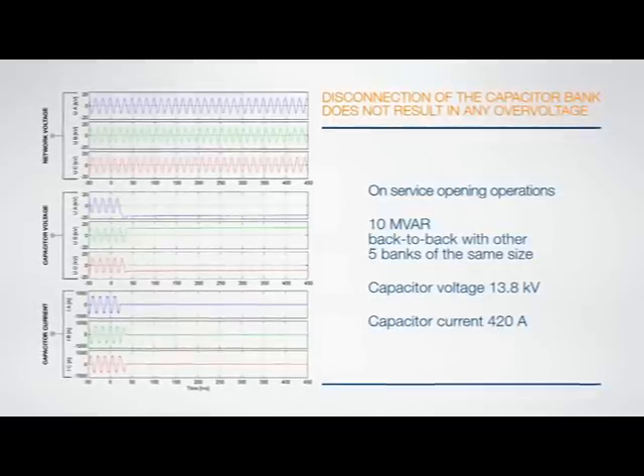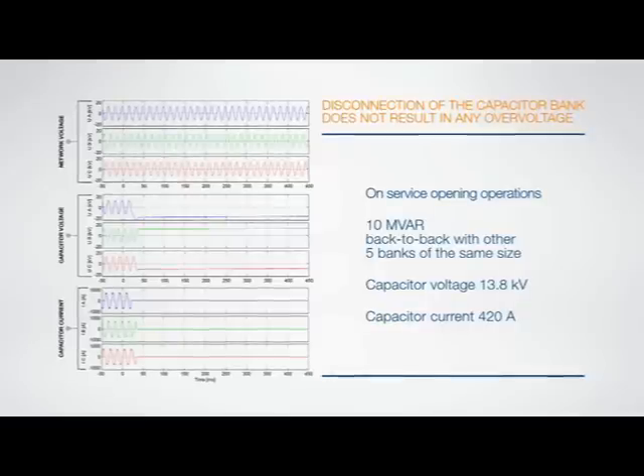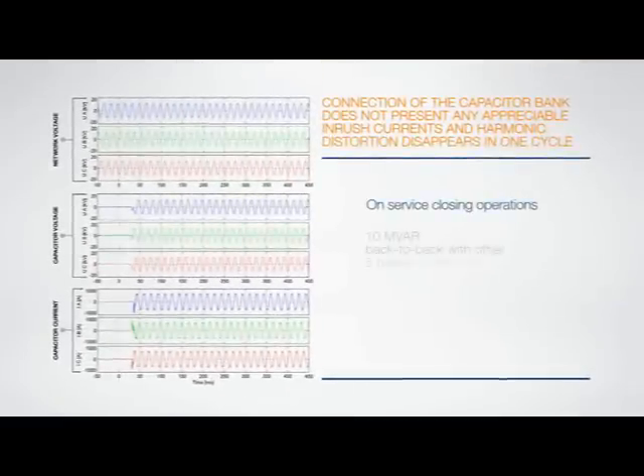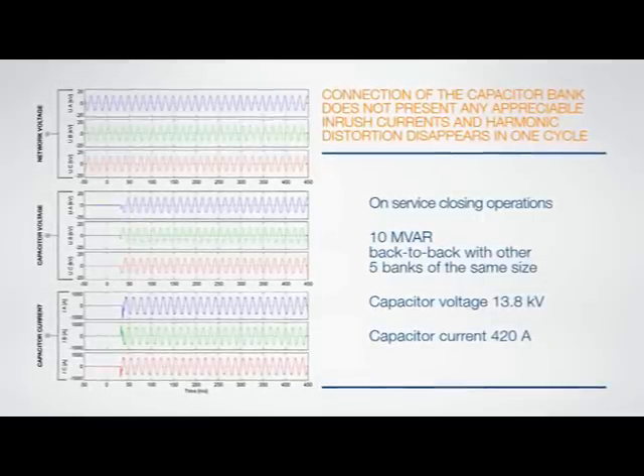These oscillograms, originating from a substation owned by a well-known American utility company, show the voltage and current of the three phases downstream of the DS1. The disconnection of the capacitor bank does not result in any overvoltage. The current is cut off precisely when it reaches zero. Connection of the capacitor bank does not present any significant inrush currents, and harmonic distortion disappears in one cycle.